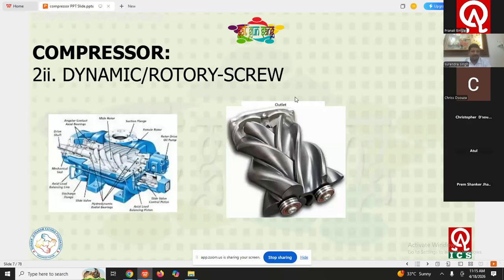The third one is the screw type rotary compressor. There is no difference from the previous slide, only the construction is different. In this compressor, in place of the lobe type, we have the screw type. So once this screw rotates in this side, the second screw rotates in the opposite side, and further on we get the compressed air from this discharge flange.